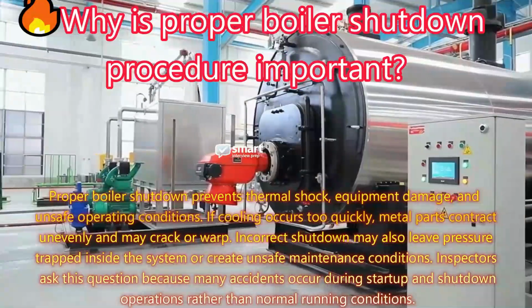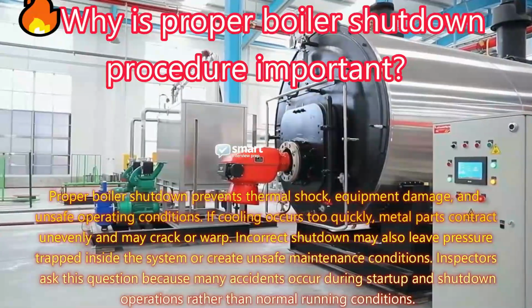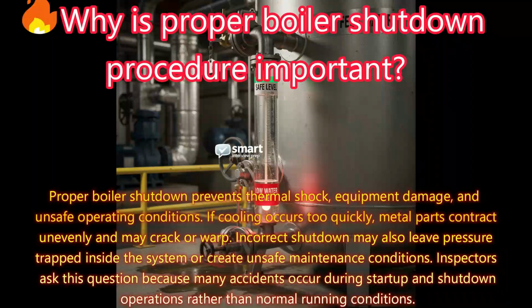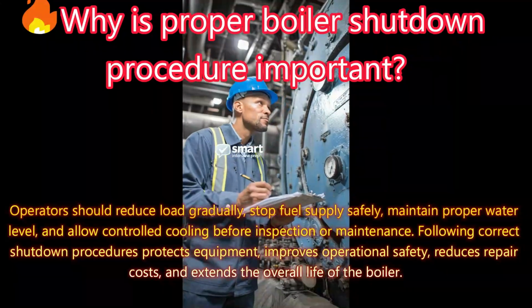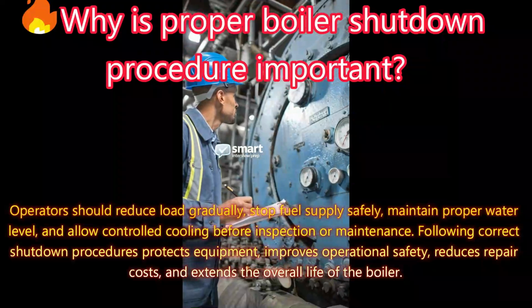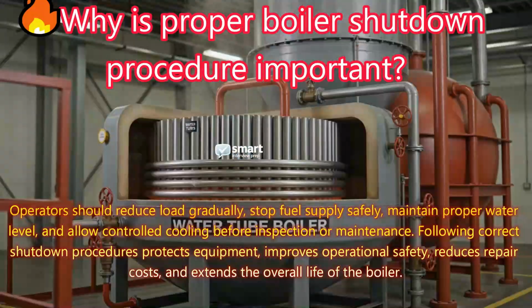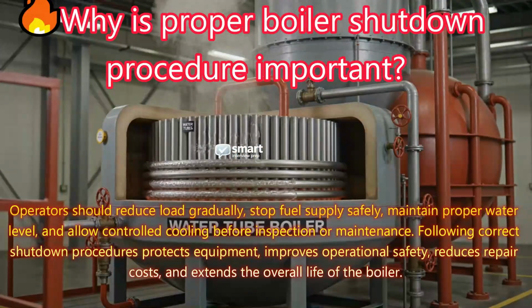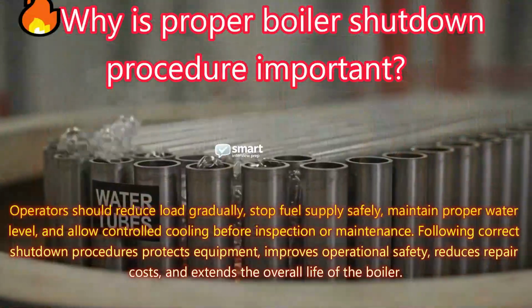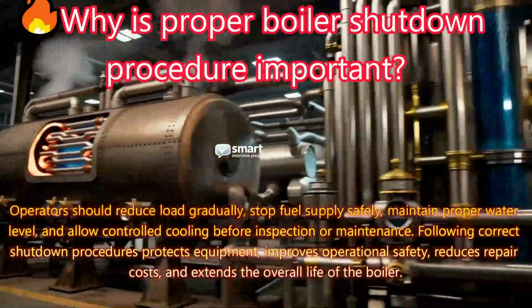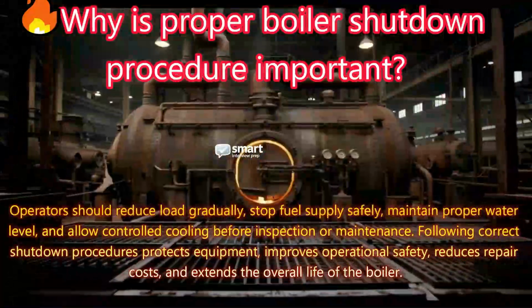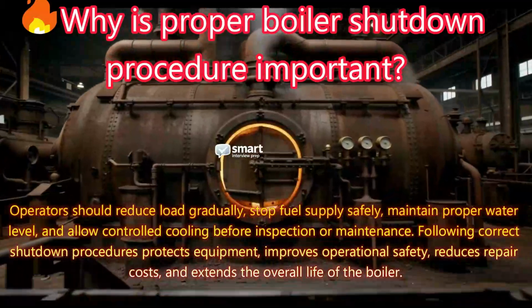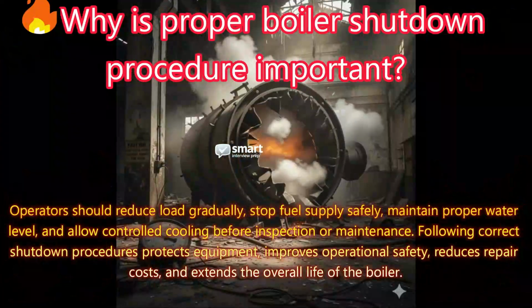Inspectors ask this question because many accidents occur during startup and shutdown operations rather than normal running conditions. Operators should reduce load gradually, stop fuel supply safely, maintain proper water level, and allow controlled cooling before inspection or maintenance. Following correct shutdown procedures protects equipment, improves operational safety, reduces repair costs, and extends the overall life of the boiler.